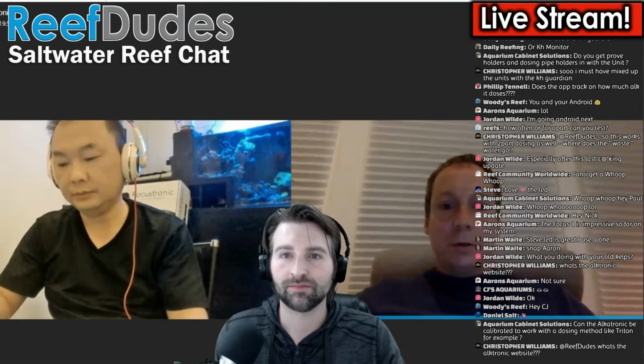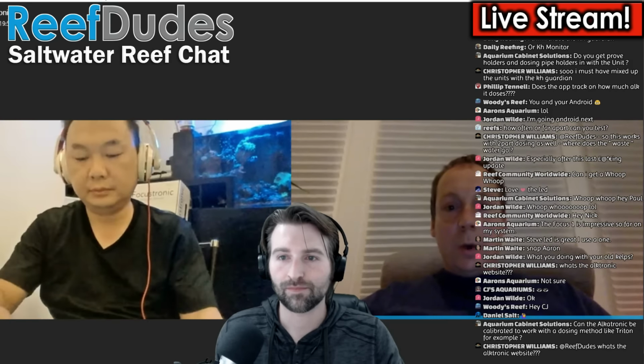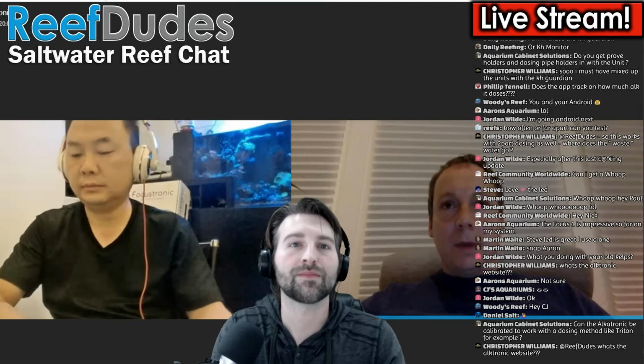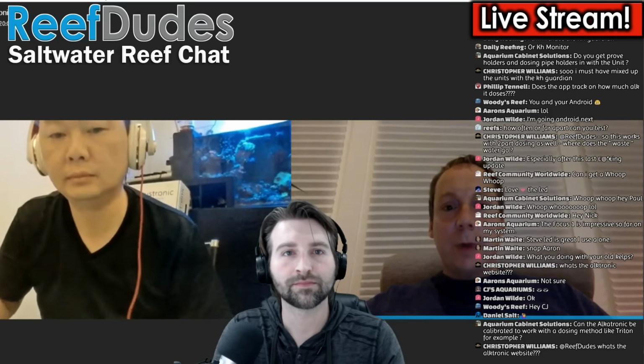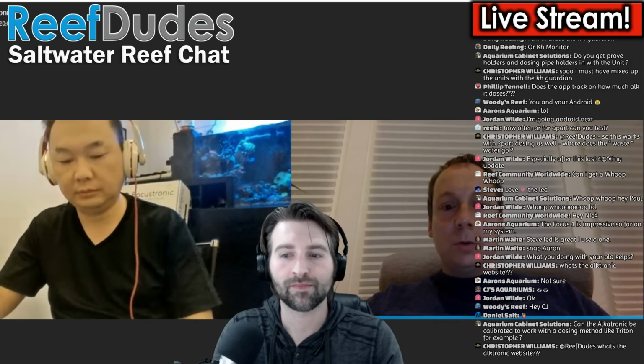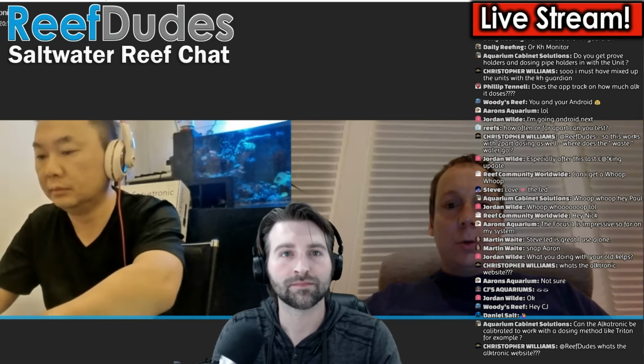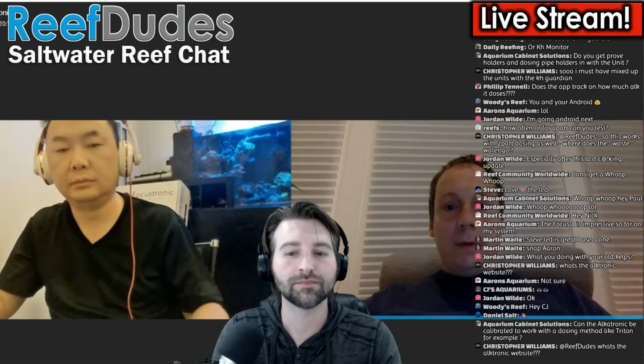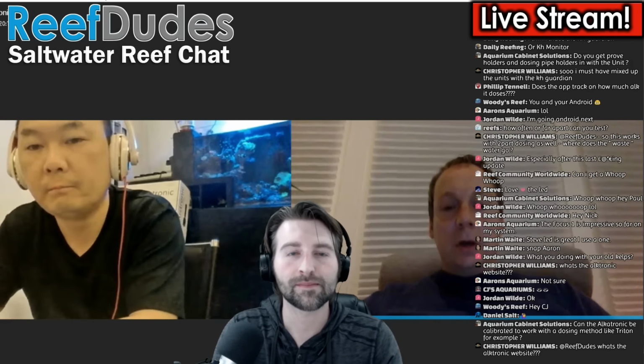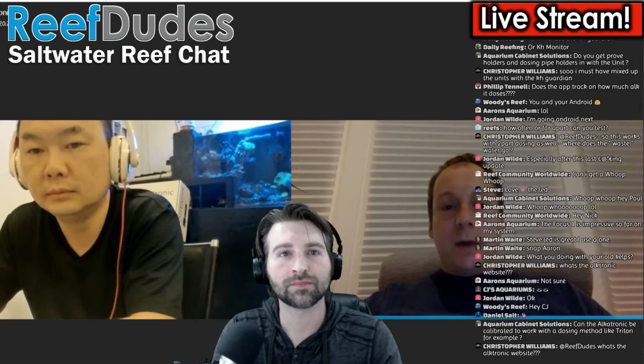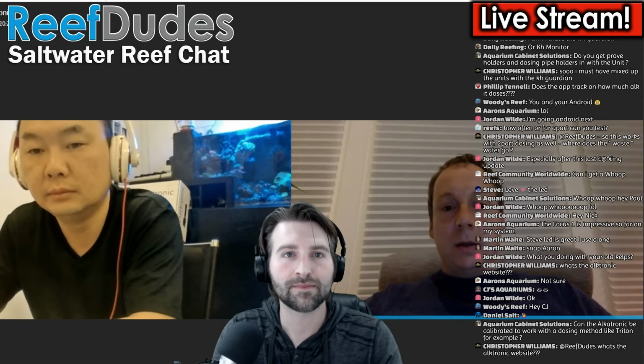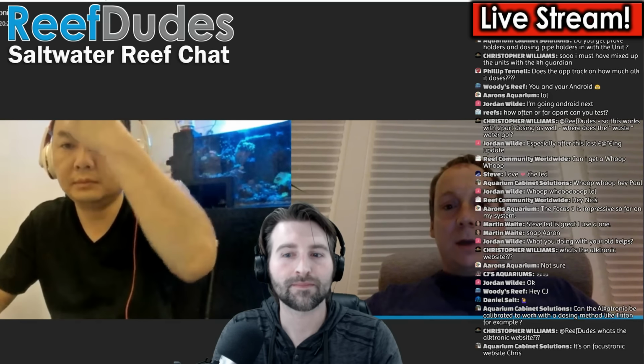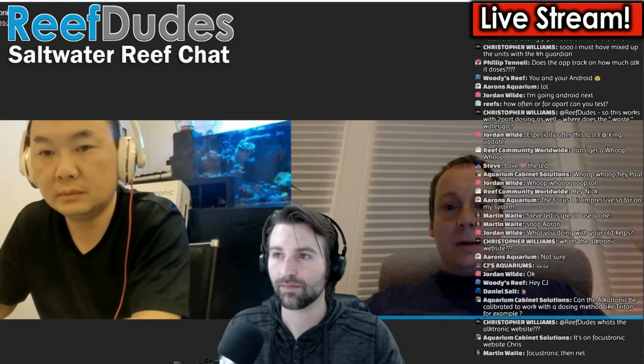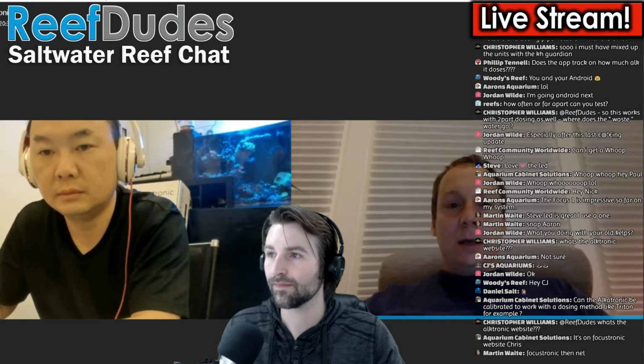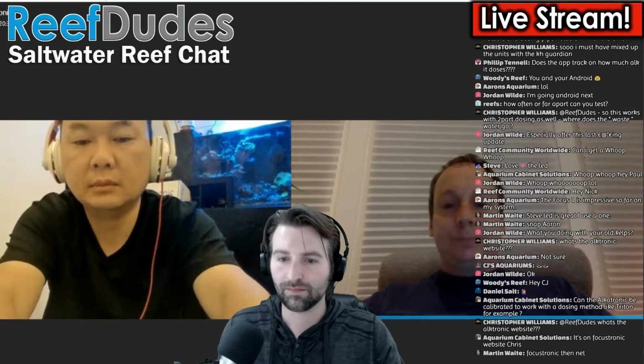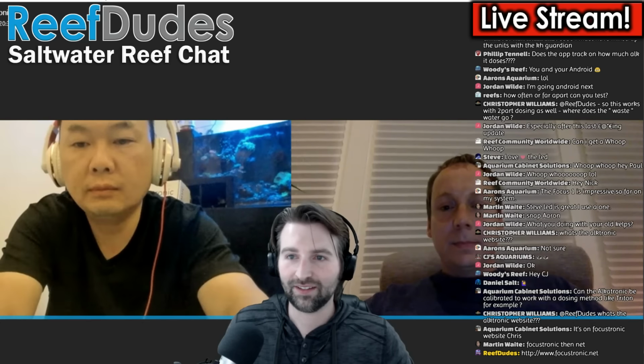And I can mention something about the alkalinity dosing. We have an algorithm which makes the increase of the alkalinity in a smooth way. The machine will not always do everything at the same time, to avoid a too rapid increase in the alkalinity. So if you, for instance, lack 0.5 alkalinity, the machine will do 0.25 first, then measure a little more often, and dose in a smooth way, so you will come up to the end point. Okay, excellent. That's a nice way of hearing about it.